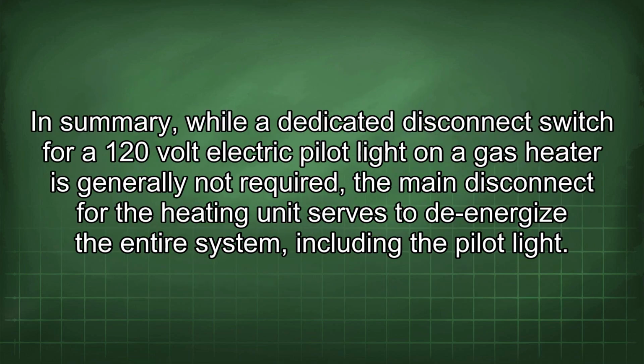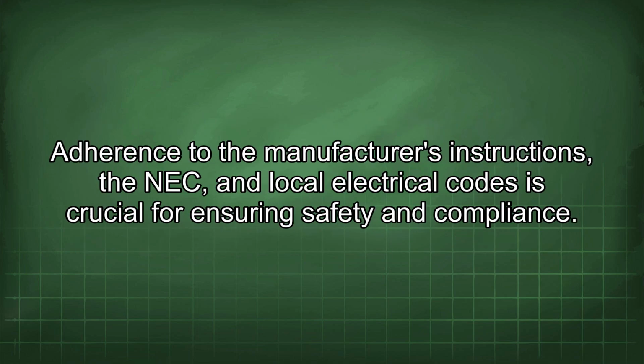In summary, while a dedicated disconnect switch for a 120-volt electric pilot light on a gas heater is generally not required, the main disconnect for the heating unit serves to de-energize the entire system, including the pilot light. Adherence to the manufacturer's instructions, the NEC, and local electrical codes is crucial for ensuring safety and compliance.